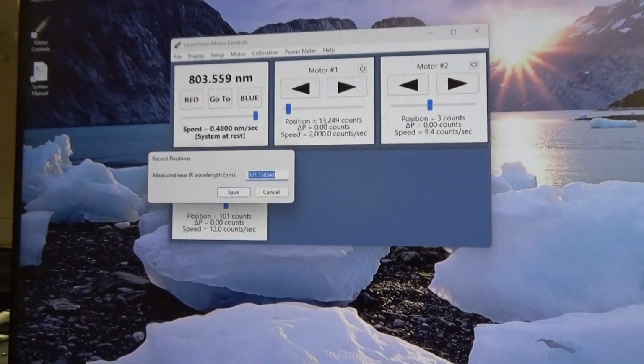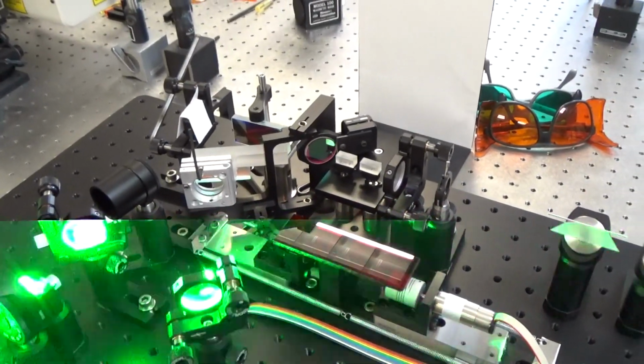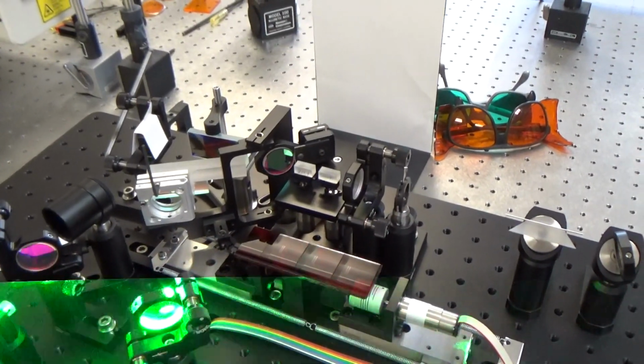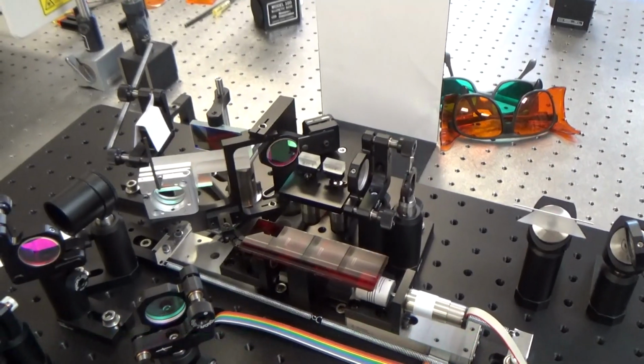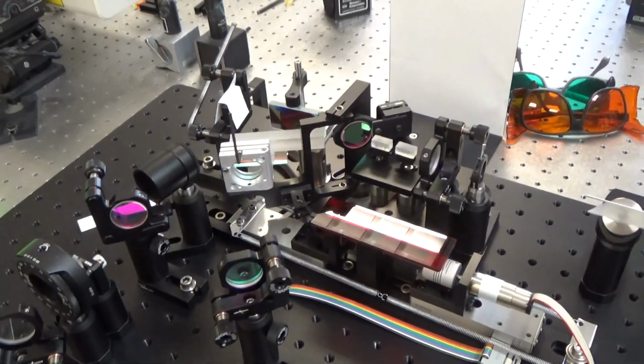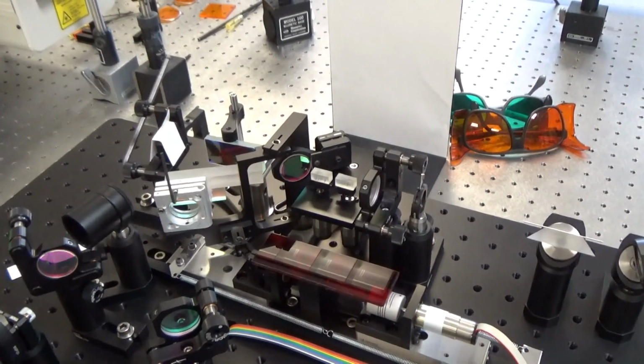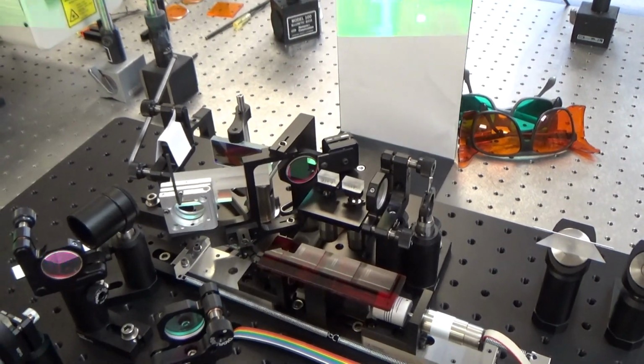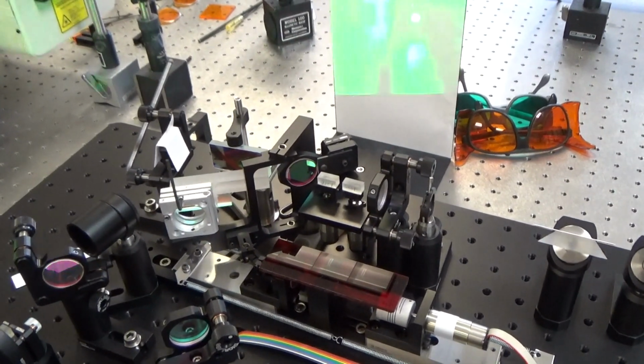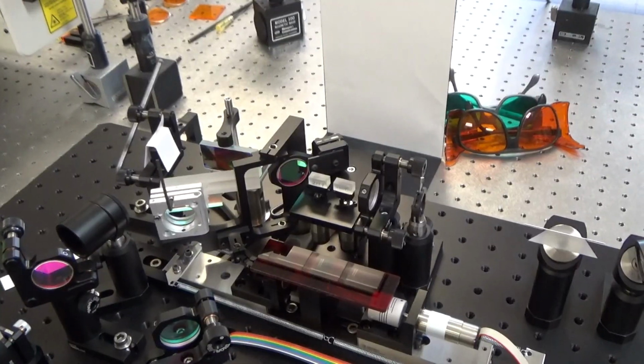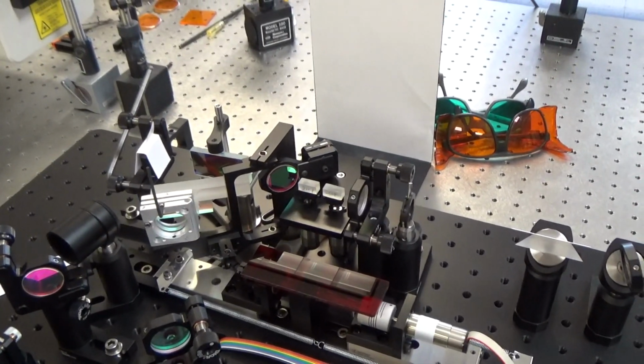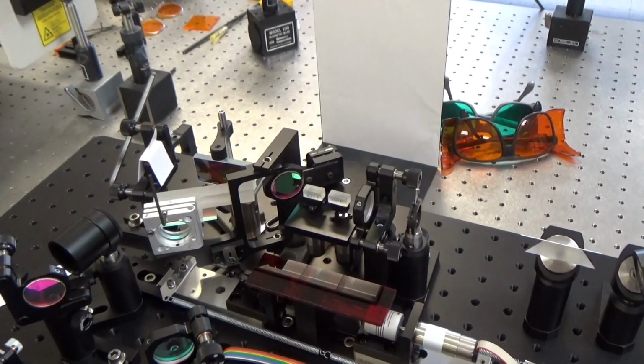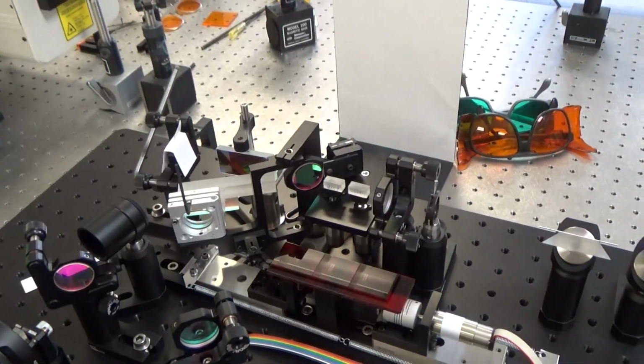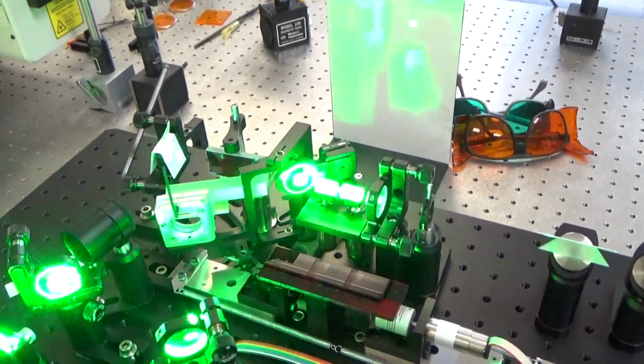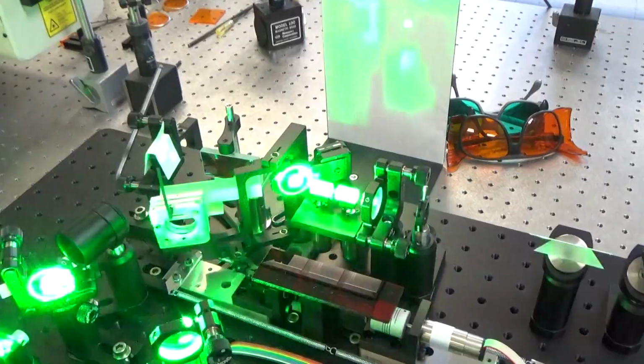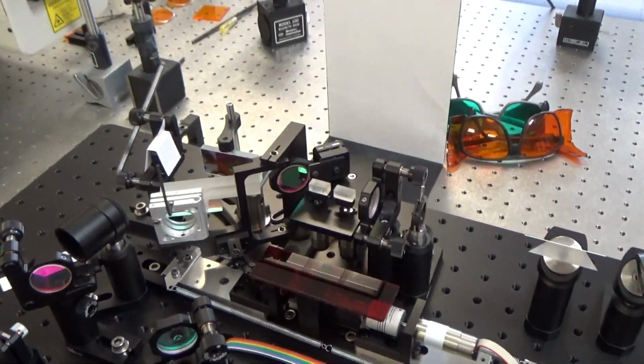So, before beginning the calibration, you should let the oscillator warm up for about 5 minutes while pumping with full energy. This is because a small amount of the green is absorbed by these crystals, and they need time to get to thermal equilibrium. The temperature of the crystals does slightly affect the tuning behavior, and so you'd like them to be at the operating temperature.